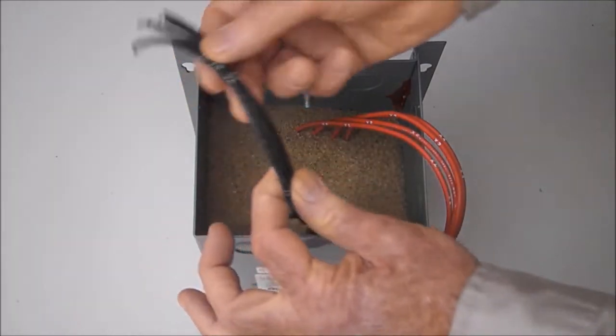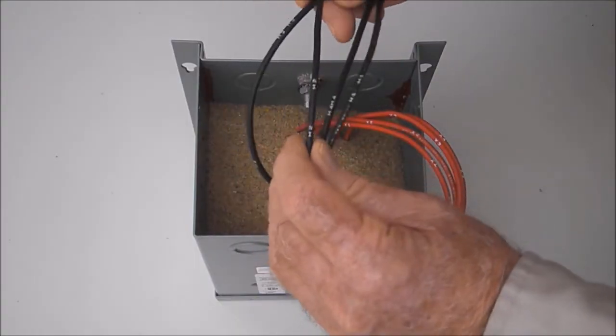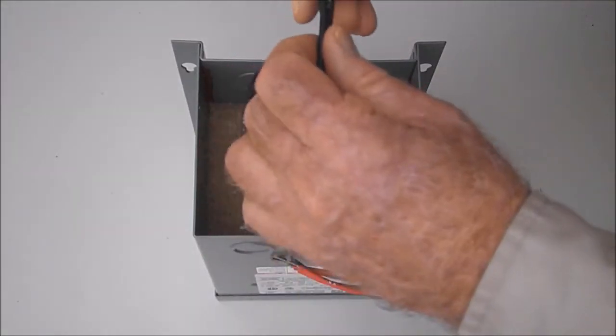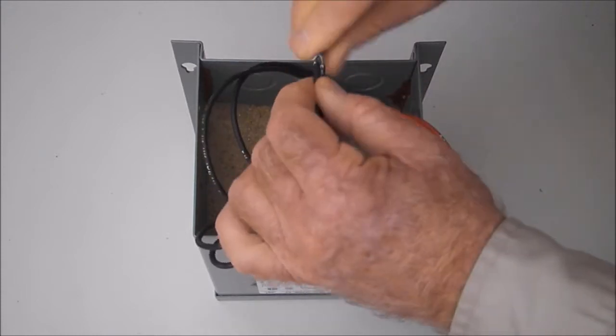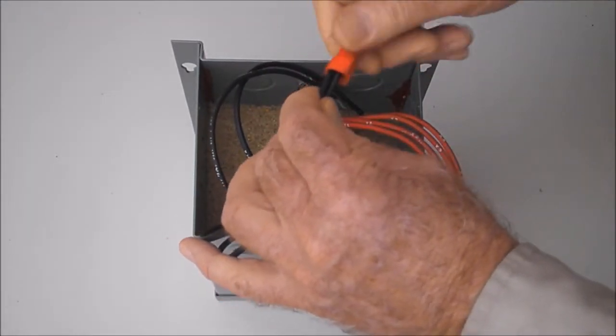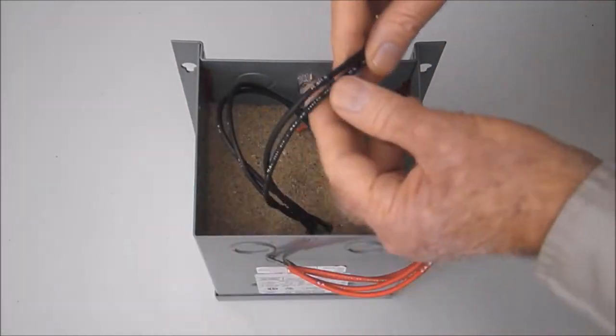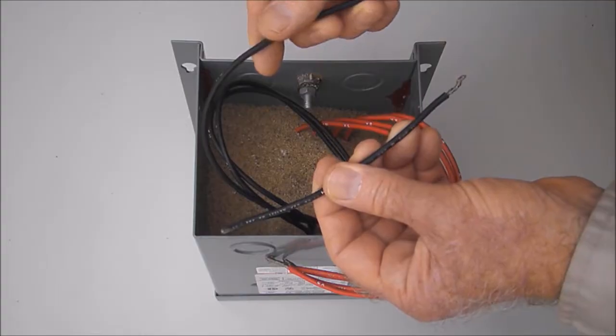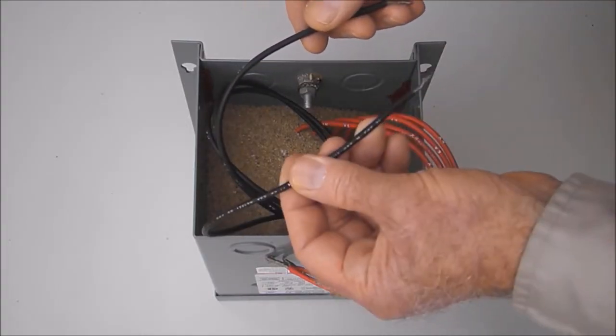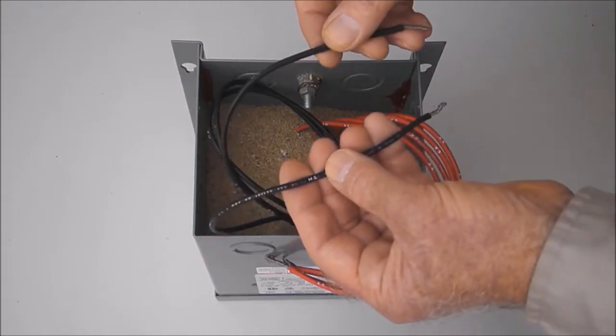We're going to start with the very popular 480 volt input on the primary. We're going to connect H2 and H3 together and tie them up with a wire nut, which leaves H1 and H4 as our 480 volt input. So one line of 480 volts will come in on H4 and the other will come in on H1.